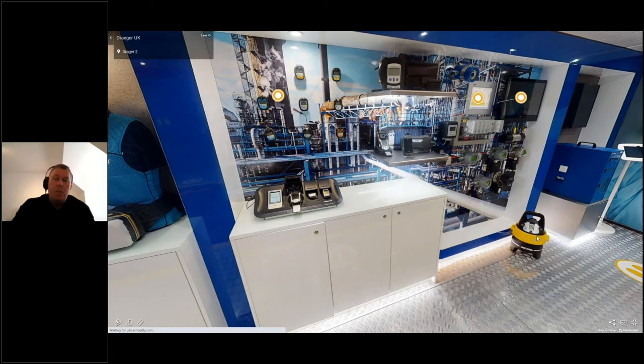At the very top of our multi-gas range, we've got the X-am 8000, seen up here on the shelf. This is our most advanced multi-gas detector with our widest range of sensors. It's ideal for clearance measurements, measures up to seven gases at the same time, and provides dual range LEL and volume for flammable gas — ideal for purging applications, for example. There's also a PID sensor option to monitor volatile compounds, including carcinogens such as benzene.